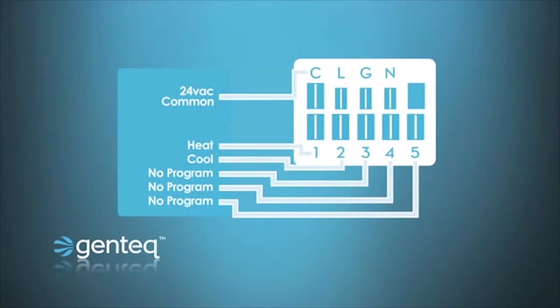So as I mentioned before, this connection block will always be the same. There's always the potential for 5 speeds or torque settings out of the X13 motor. However, the manufacturer only has to program the ones that the system that they're putting the motor in require. Being that this is a gas and AC only package system, it simply needs a heat speed and a cool speed for proper operation.